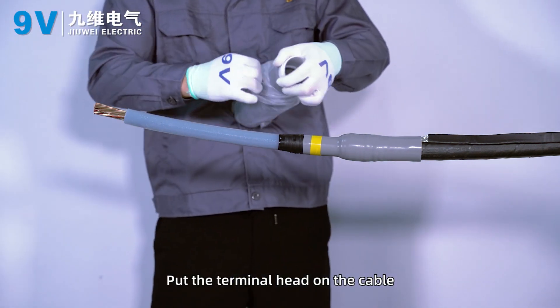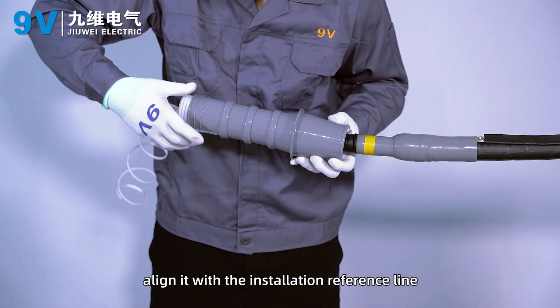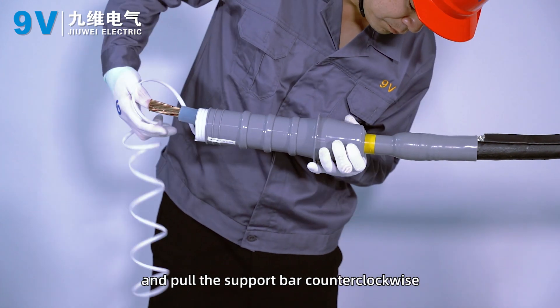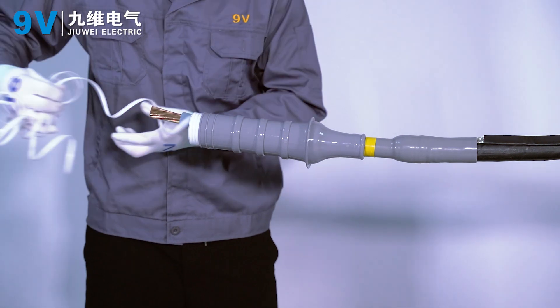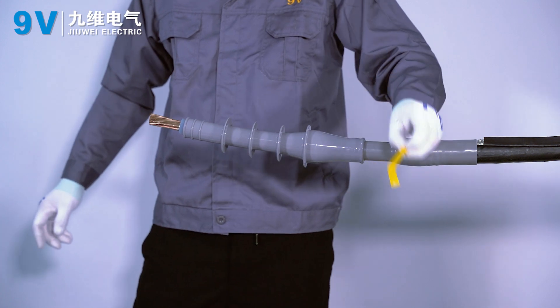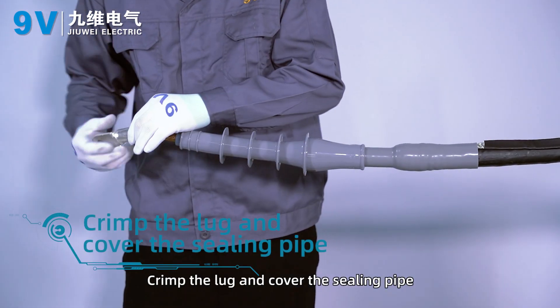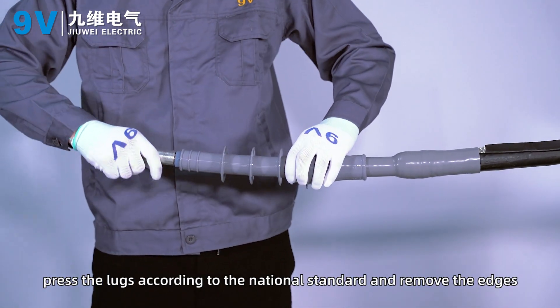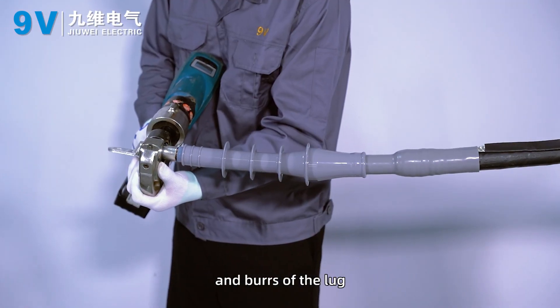Put the terminal head on the cable and align it with the installation reference line. Pull the support bar counterclockwise to shrink the terminal head. Remove the edges and burrs of the lug, cover the lugs, and press the lugs according to national standard.